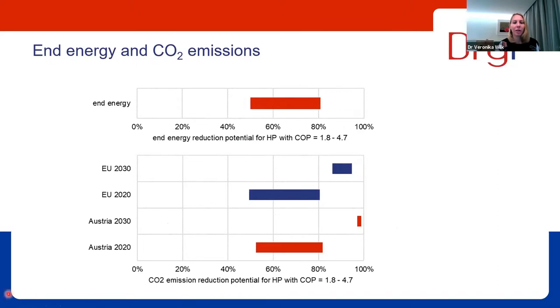And we see here that we can achieve end energy savings ranging from 50 to more than 80% with a heat pump if it replaces a natural gas burner. And this is a very interesting potential. In terms of emission, the result is quite similar.